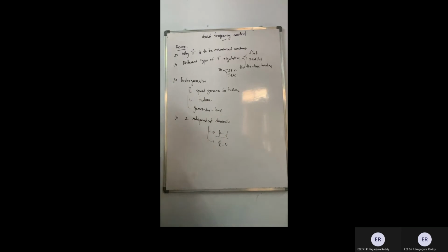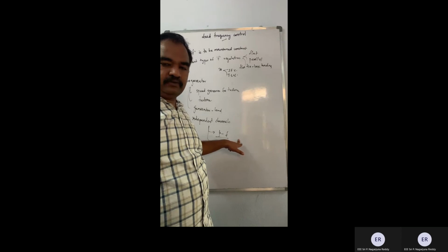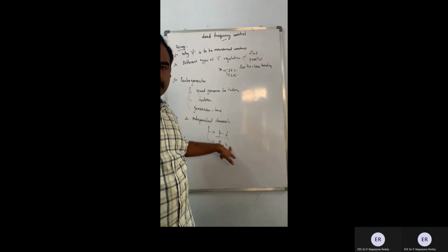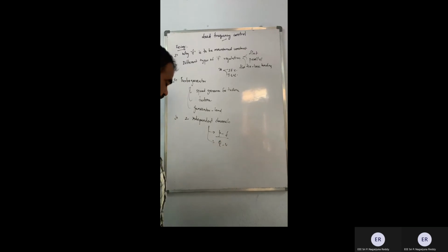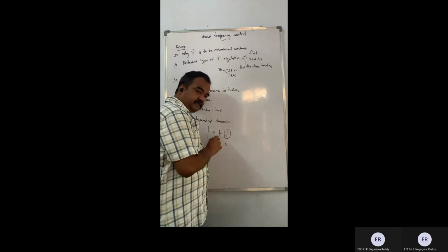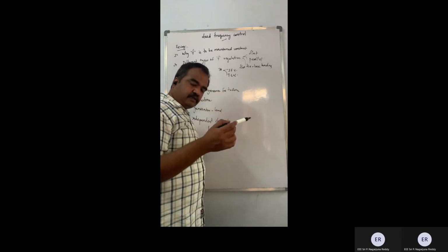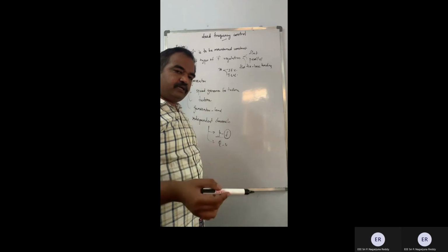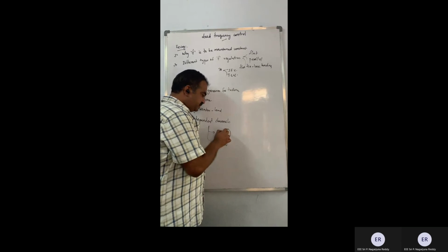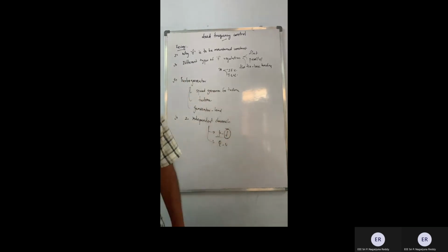When we are concentrating on the P-f channel, any changes in the active power will lead to change in the frequency. Any change in the reactive power will lead to change in the voltage. So now our target is to regulate the frequency. If any change in power is there, let us suppose because of demand, you are supposed to overcome it by raising your generation or by lowering your generation. And you are supposed to make sure that f remains constant. Okay.